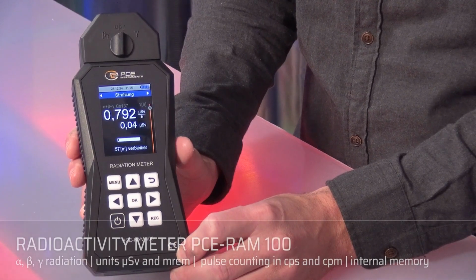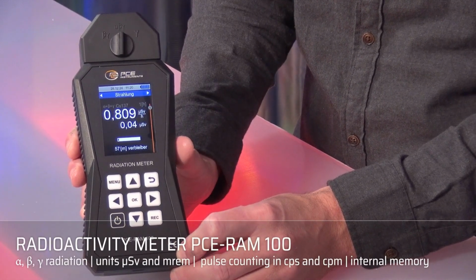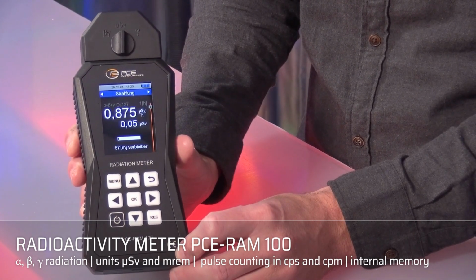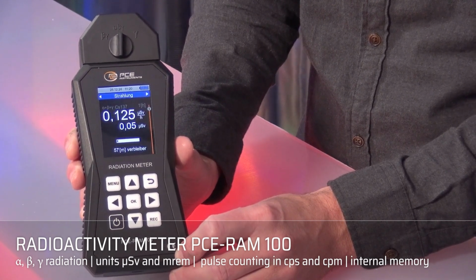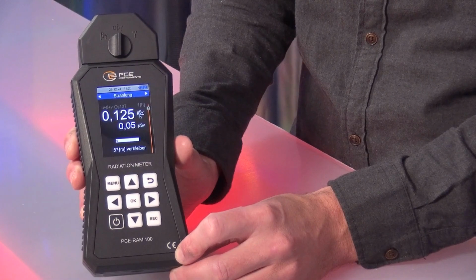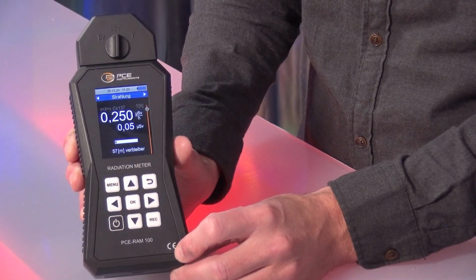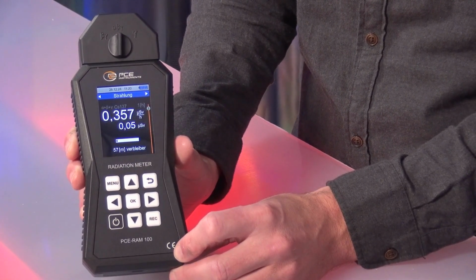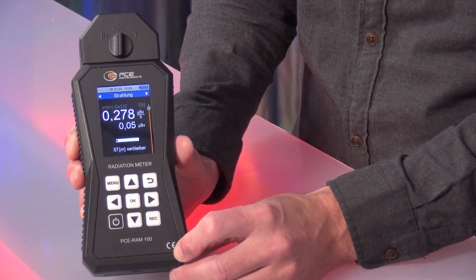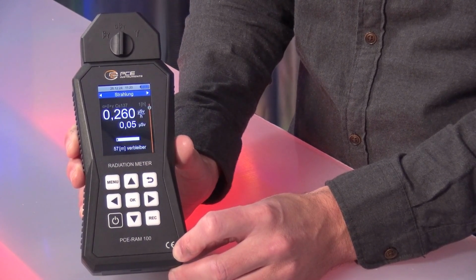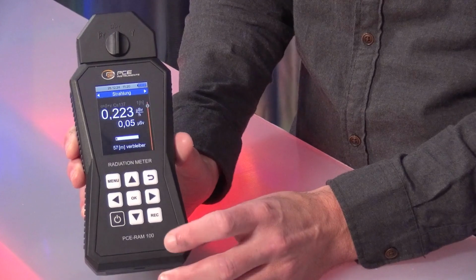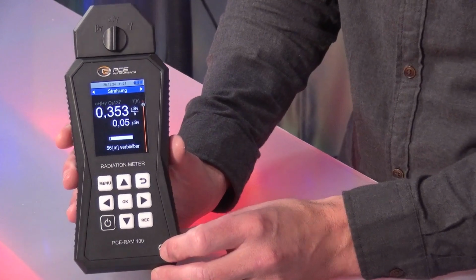I am holding the PCE-RAM 100 in my hands. This is an extremely high-quality radiation meter for alpha, beta, and gamma radiation, in a range from 0 to 1,500 microsieverts per hour. It has a resolution of 0.001 microsieverts per hour. It also has a second range, where it measures up to 9.9 sieverts with a slightly lower resolution. We can see a switch, a manual switch, at the top of this device.